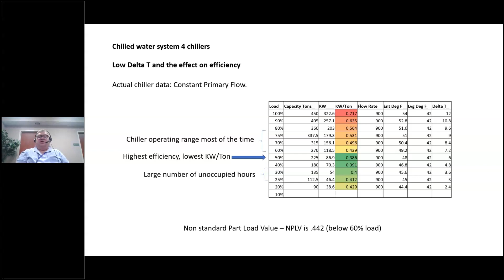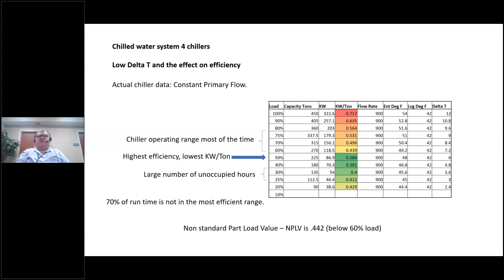So here's an ECM. You've got to find a way to get this machine to operate in its most efficient range. But what I'm going to tell you is that this is one of 4 chillers, and we looked at this across all 4. So potential ECMs: variable speed, variable flow will benefit this application. Remember, the minimum flow requirements keep a chiller online at low flow. Plus, you don't want to operate on that low end a lot of the time. Variable flow will improve the temperature difference across the chiller and plant.